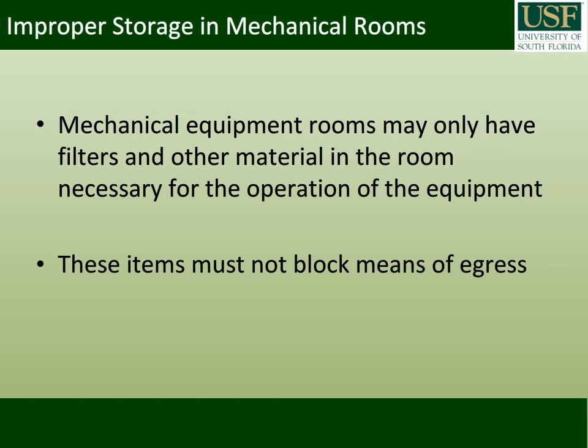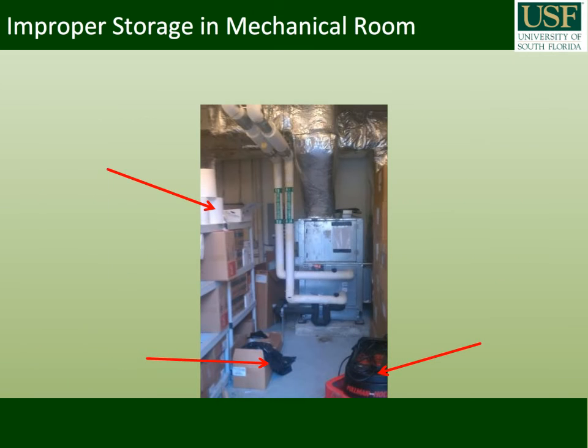Improper storage in mechanical rooms. Mechanical equipment rooms may only have filters and other material in the room necessary for the operation of the equipment. But make sure these items do not block egress. Following the red arrows we can see items that do not belong in this mechanical room. We see paper towels at the top, and trash bags and a shop vac at the bottom.